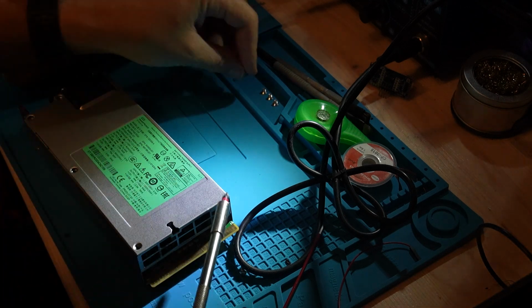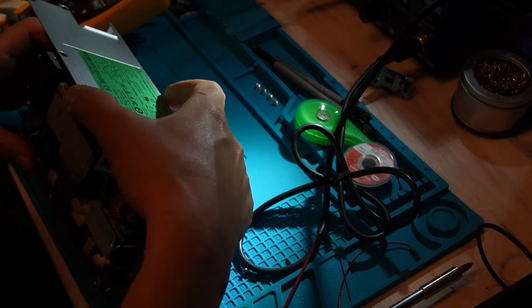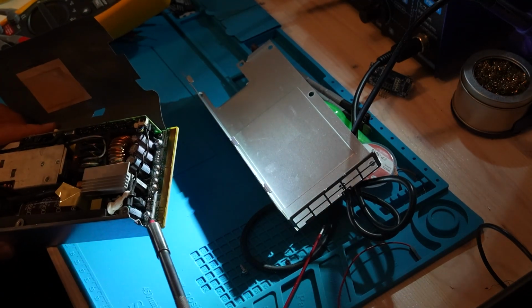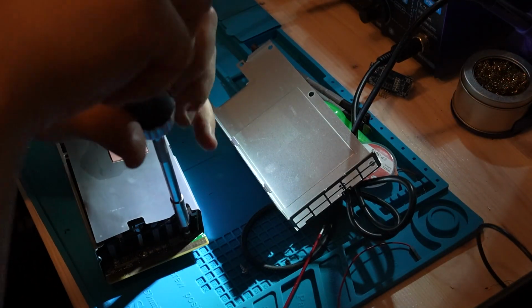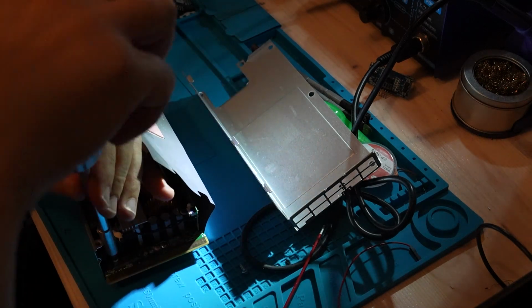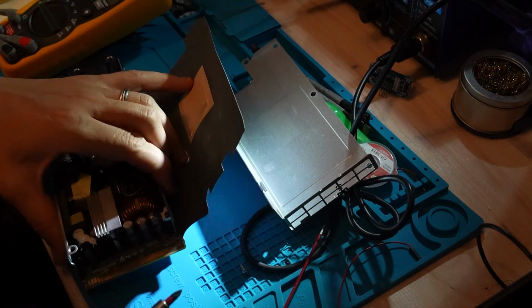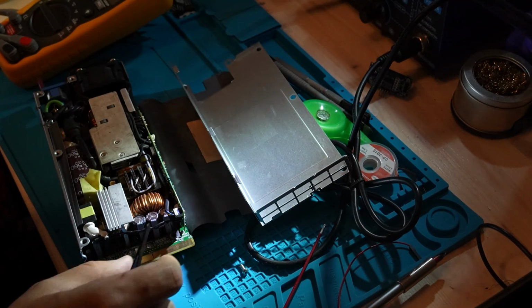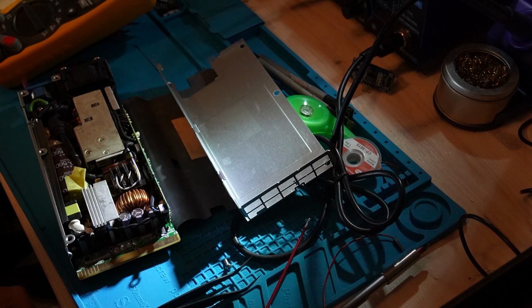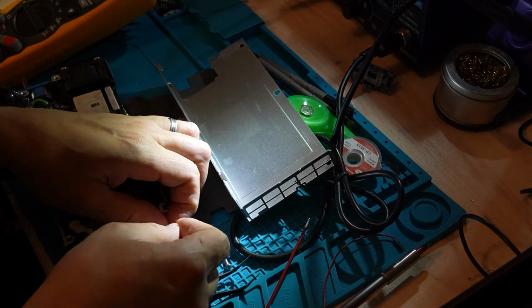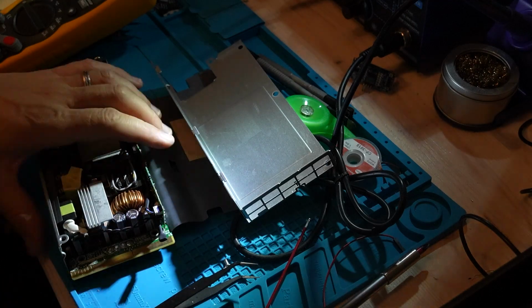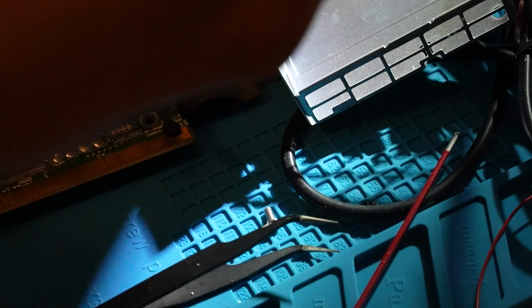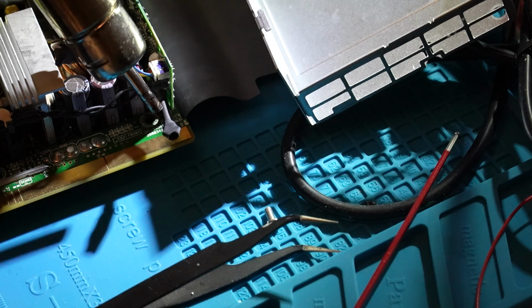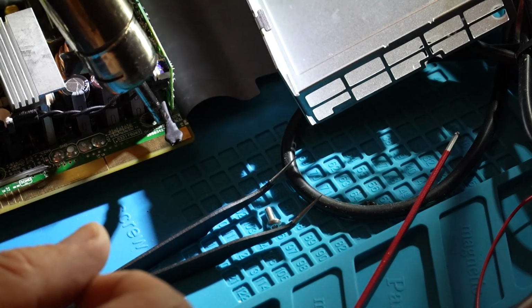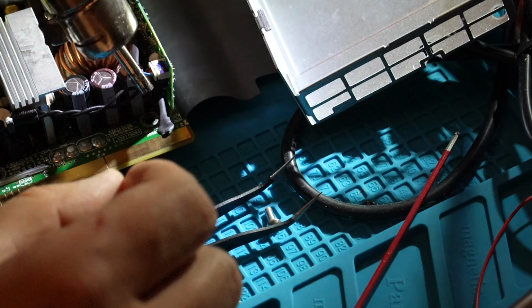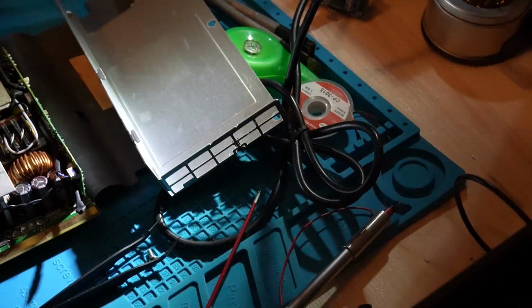Safety disclaimer: we are working with high current, high power supplies. Be extremely careful even when disconnected. These supplies have large capacitors that can hurt or even kill you. Work safely, double check everything, and understand what you are doing. The connections shown in this video are for powering machines using up to 500 watts. If your application requires more power, adjust your wire gauge accordingly and use dedicated power cables for each load instead of splitting a single cable like I will show here. Always do your calculations and be careful when working with high voltage and high current.